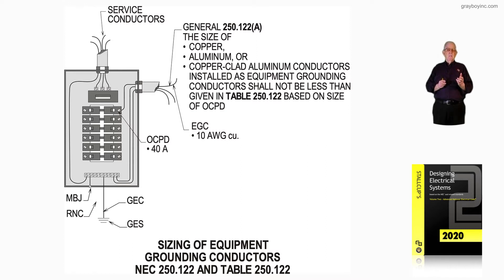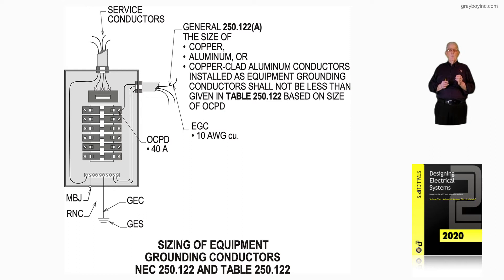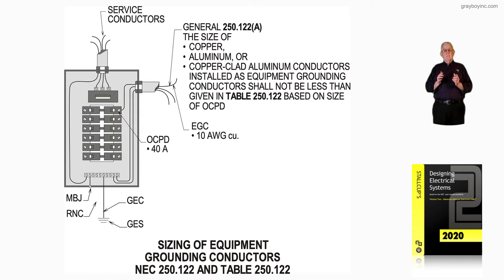In the service equipment, we have a 40-amp overcurrent protection device. Based upon a 40-amp overcurrent protection device, a number 10 equipment grounding conductor must be selected and used per Table 250.122. That is what illustration 16-113A is illustrating — how to size an equipment grounding conductor when an overcurrent device is ahead of the circuit conductors. This is, of course, load side.